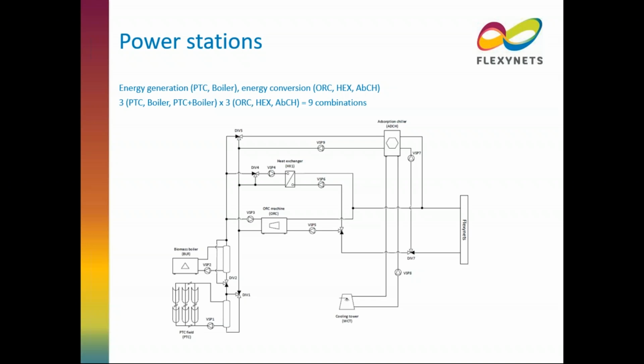This is just one case, but it is interesting to stress that traditional CHP is not the best solution to be coupled to this type of network. Indeed, even if a lower temperature network can be beneficial from the point of view of cogeneration cycles, because a lower condensing temperature increases the electric efficiency of the engines, the presence of heat pumps requires the consumption of additional electricity, so that the overall balance of the system makes the use of traditional CHP units within FLEXYNETS a little bit questionable.